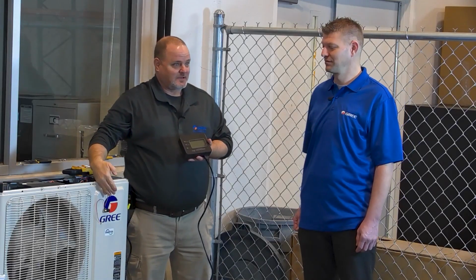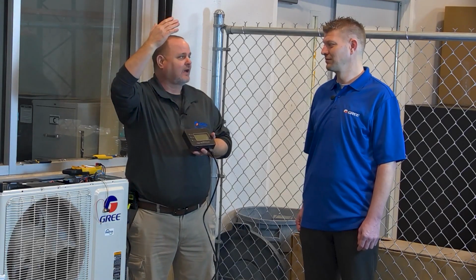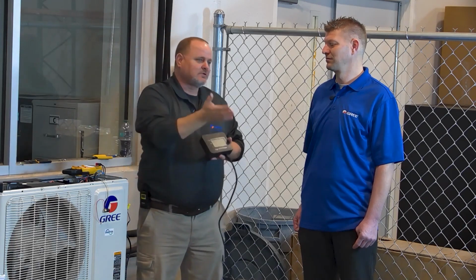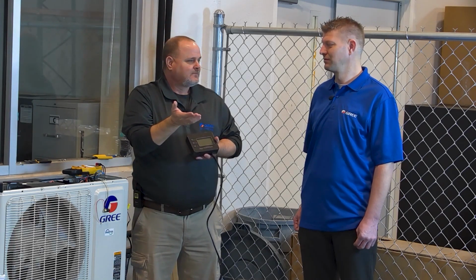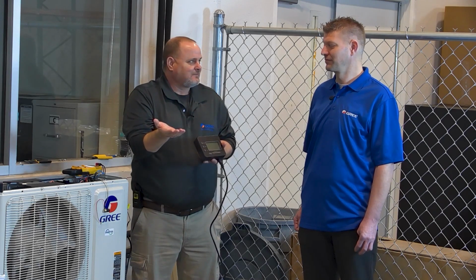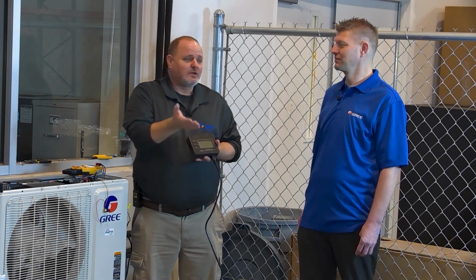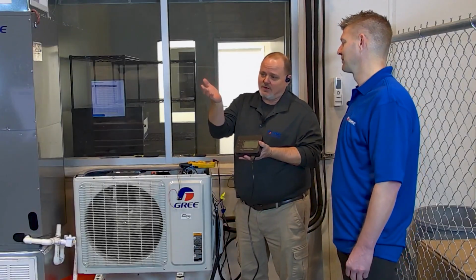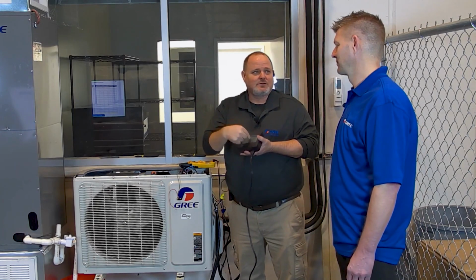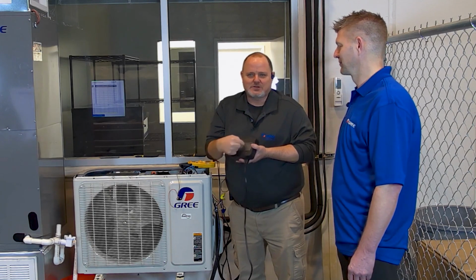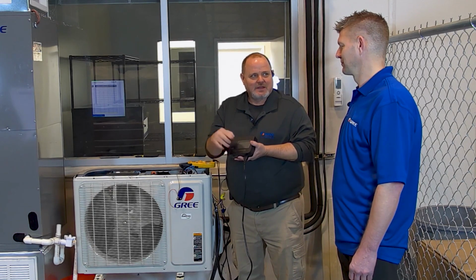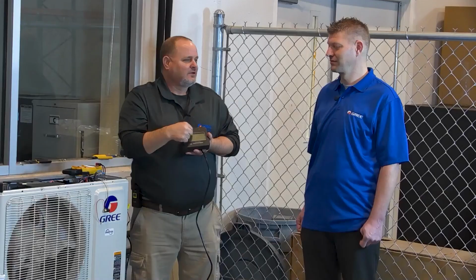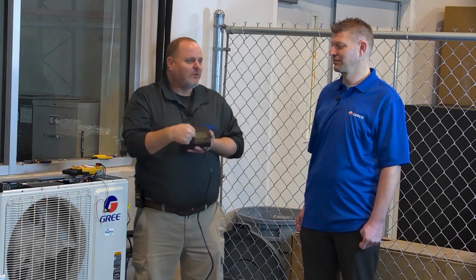Discharge temperature sensor. We talked about that. If we're starved of refrigerant, our discharge temperature is going to be too high. If we're overcharged, our discharge temperature is going to be too low. That's superheat. It's total low side superheat, including heat of compression, right? Yep. So if it's total low side heat including heat of compression, this gives you the discharge temperature. So if you start learning what normal discharge temperature should be in a loaded condition, you'll know when it's too hot and you'll know when it's too cold.